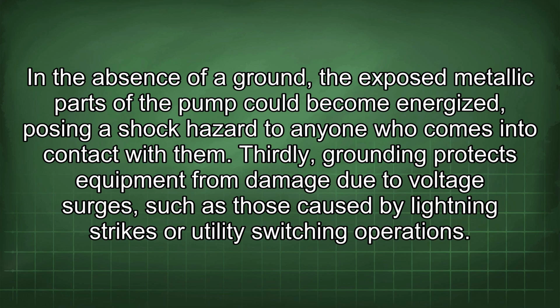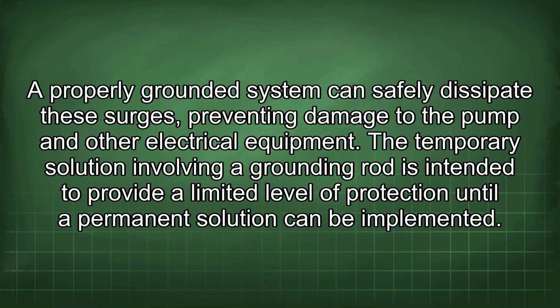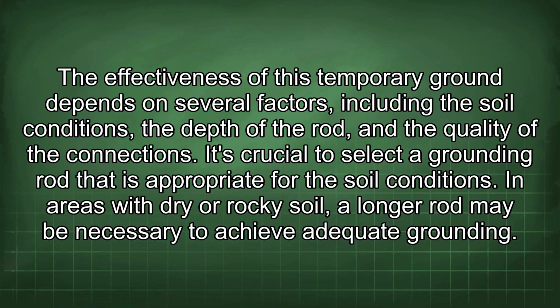Thirdly, grounding protects equipment from damage due to voltage surges, such as those caused by lightning strikes or utility switching operations. A properly grounded system can safely dissipate these surges, preventing damage to the pump and other electrical equipment. The temporary solution involving a grounding rod is intended to provide a limited level of protection until a permanent solution can be implemented. The effectiveness of this temporary ground depends on several factors, including the soil conditions, the depth of the rod, and the quality of the connections.